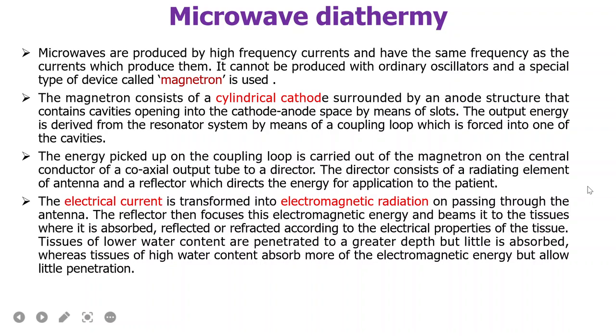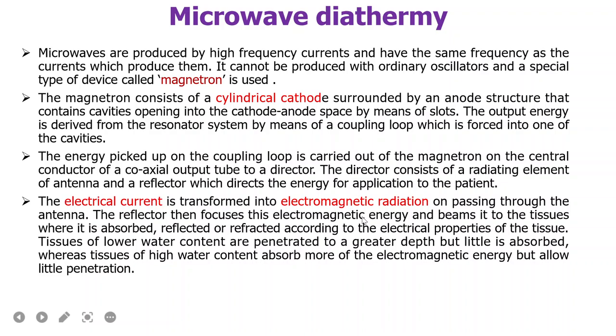A director is also used, which consists of an antenna and a reflector that directs the energy for application to the patient. The electrical current is transformed to electromagnetic radiation by passing through the antenna. Using the antenna, we are sending the electrical current as electromagnetic radiation. Then the reflector focuses this electromagnetic energy and beams it to tissues where it is absorbed, reflected, and refracted according to the electrical properties of the tissues.